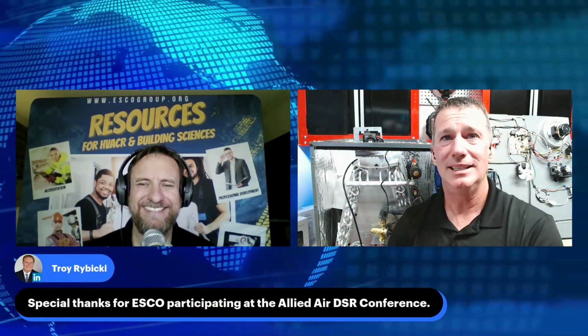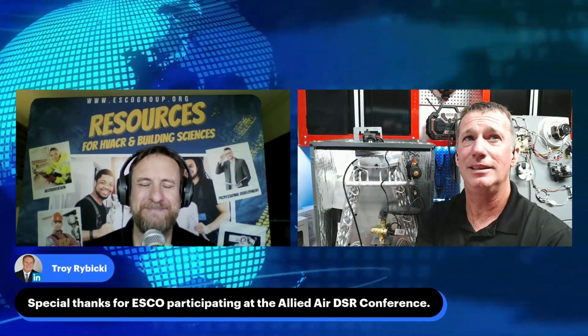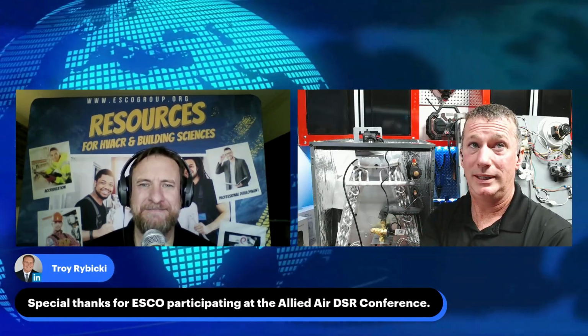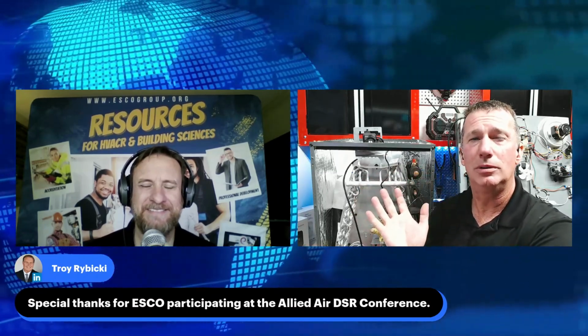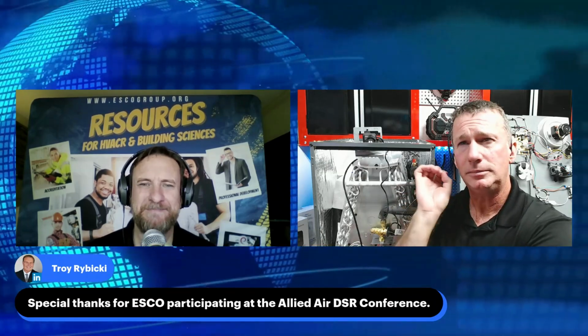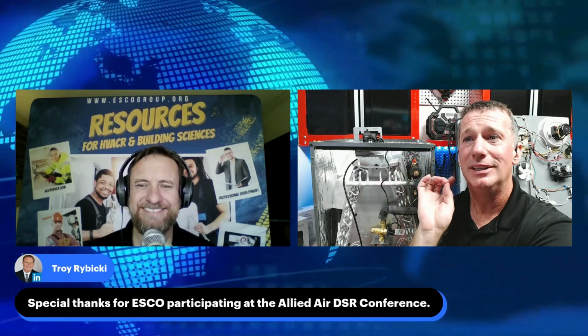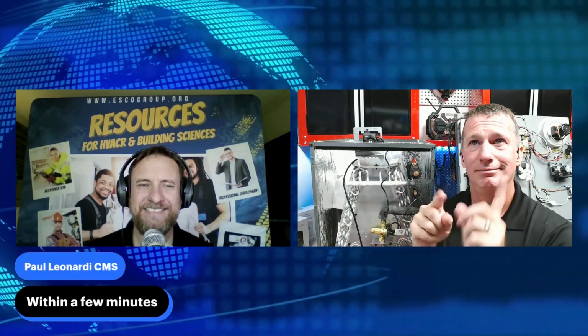So this was one of the questions I did in class quite often, asking people what they thought. And Ty, if we think about a gas appliance, how long does it take for that thing to typically initiate a state of soft lockout? Pretty quick, right? Okay. So with this particular sensor and this particular control, it actually does sampling every 5 seconds. And if it reaches the lower flammability limit, it will go into a state of soft lockout for 5 minutes. And it will initiate, within a few minutes, Paul. Exactly right. It's actually going to be, hopefully, within a 5-second period.